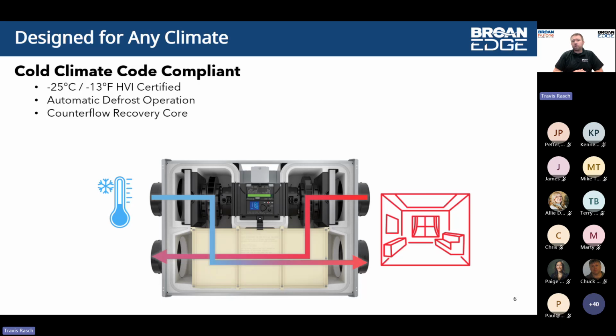You do see the counterflow recovery core, the basically off-white, I'll say yellowish rectangle shown there in this rendering. That is the recovery core. It's using what's called a counterflow technology or counterflow design. You can see how, if we look at those arrows moving to and from the outside and from the inside, the air passes through that recovery core. The recovery efficiency of a recovery core truly comes down to contact time and surface area. By going to a counterflow design, we're increasing that surface area, as well as increasing the contact time in which those two airflow streams have to interact with one another in their given air channel passages.